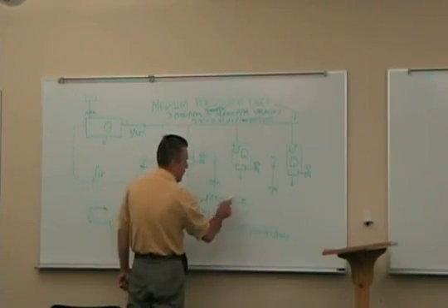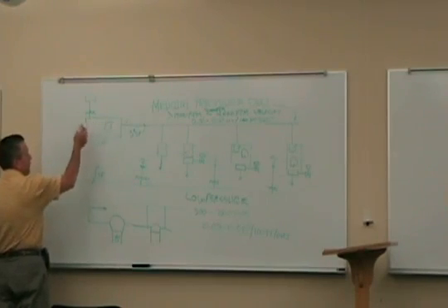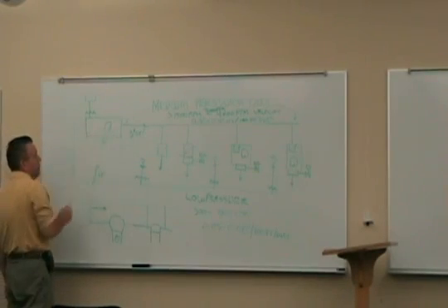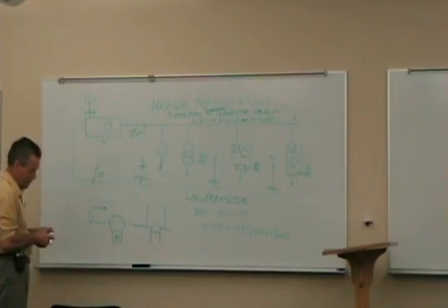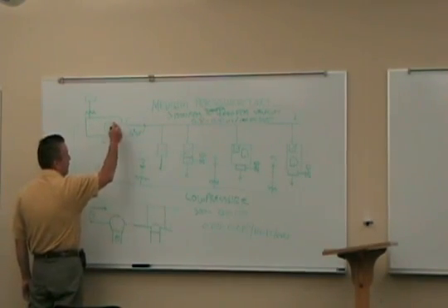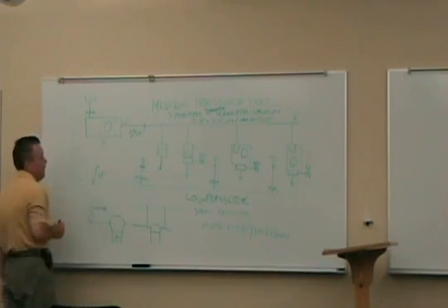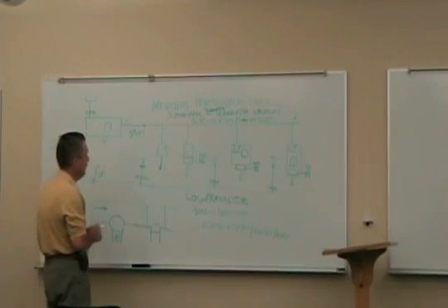This low pressure duct, you generally don't have to worry about sound except right here. The air handling unit generates a certain amount of sound pressure. Generally that's shown in the submittal documents. Looking at sound is very, very complicated in how you address it. Most people just look at the sound generated by the air handling unit, and they put silencers here or here in the duct. A silencer is just an insulated piece of duct with a lot of insulated baffles that attenuates a certain amount of sound.